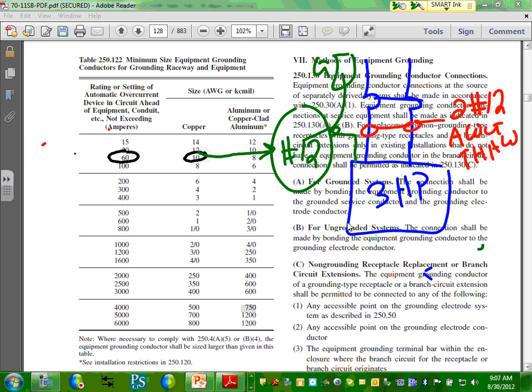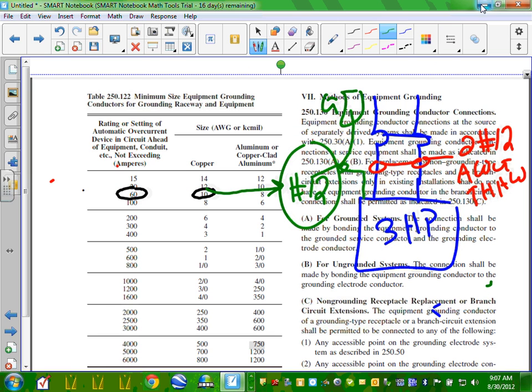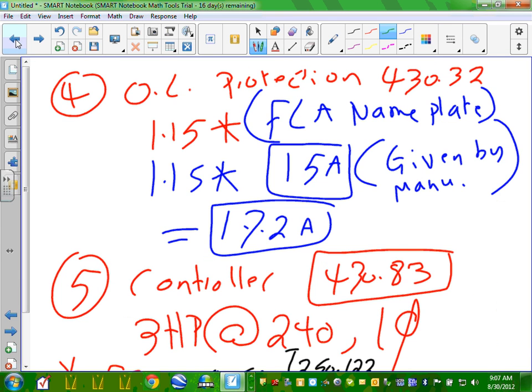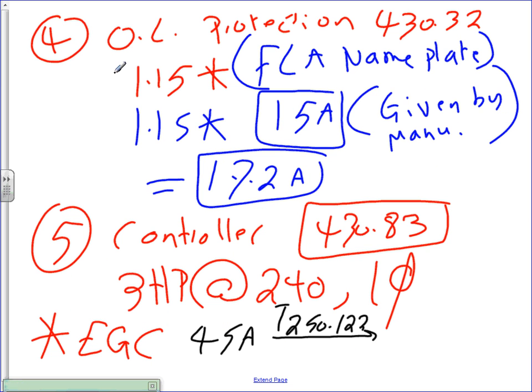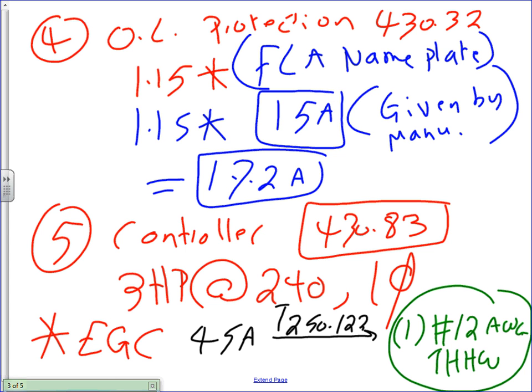So for example, this is just another example. If my panel is a 400 amp sub panel and I need to pull a ground, what's the ground? Equipment ground conductor, number 3. Okay, everybody got that one? Cool. So that's basically what my conductors are. Let's go back to my conductors and full screen. And then the conductor would be number 12 AWG THHW, done. Not number 10.